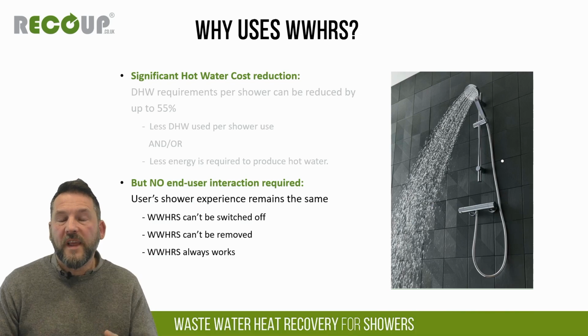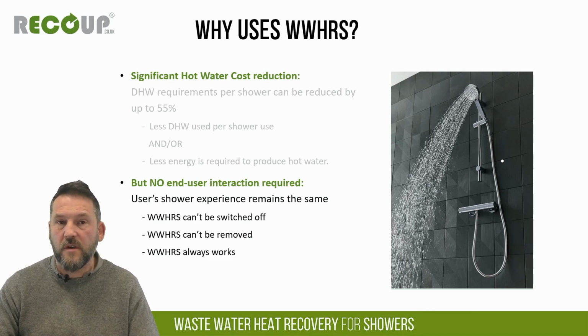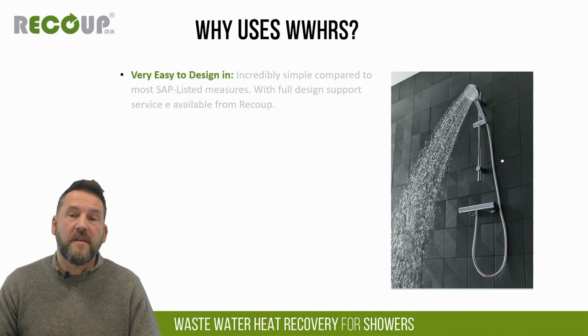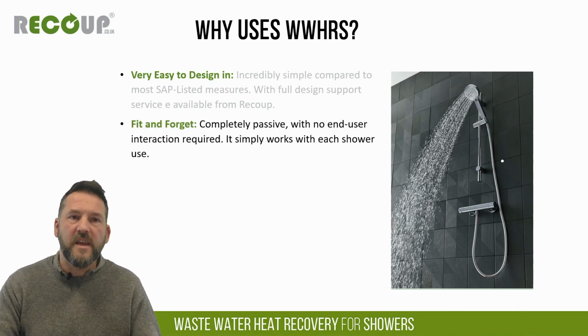And then importantly, there's no end user interaction required. So wastewater heat recovery is, for all intents and purposes, part of the plumbing infrastructure. It's a passive heat exchanger. There's no mechanical connections, no moving parts, no filters, no consumables, and so no end user interaction. So it can't be switched off, it won't be isolated, there's no filters to block up, it just works every time the shower's used. As I said earlier, it's very easy to design in.